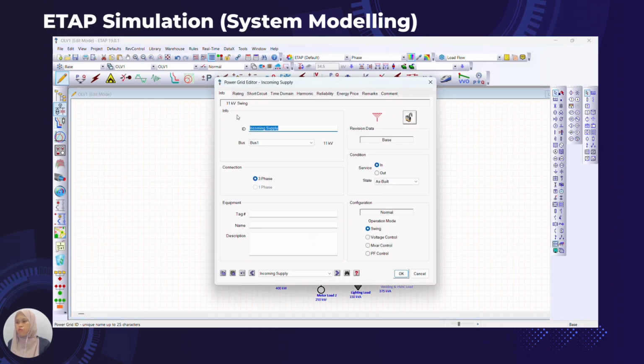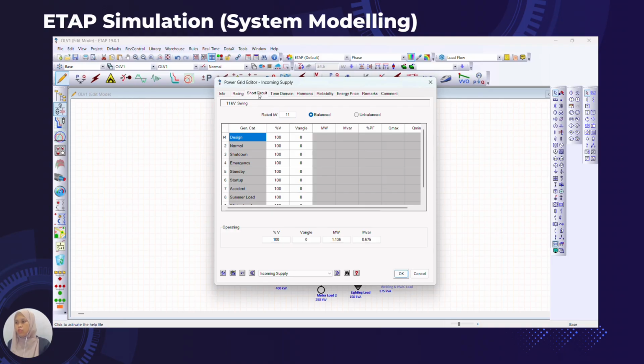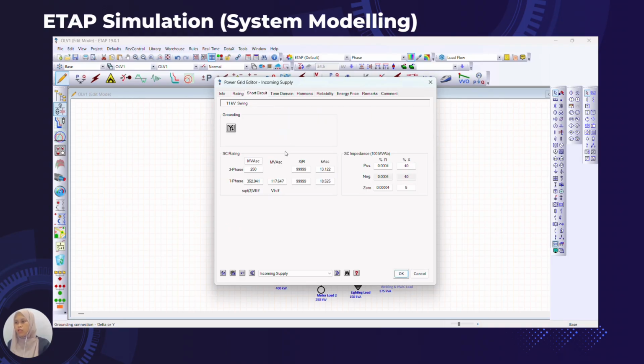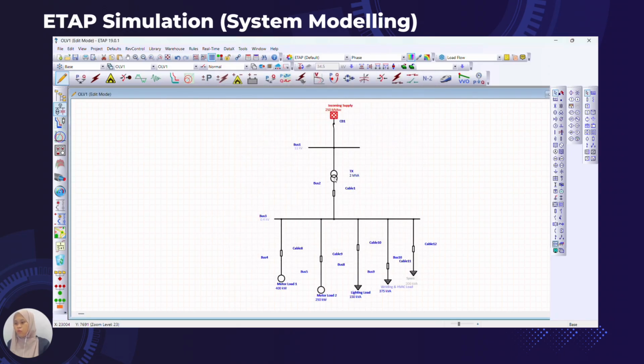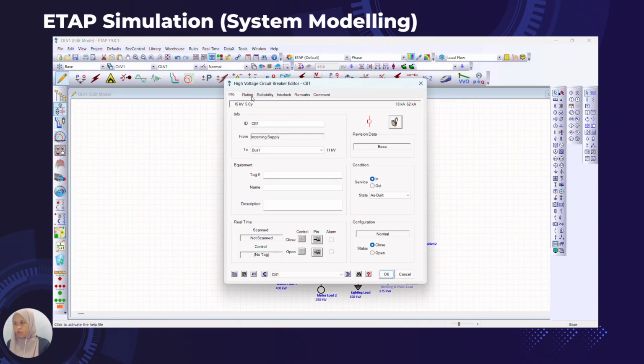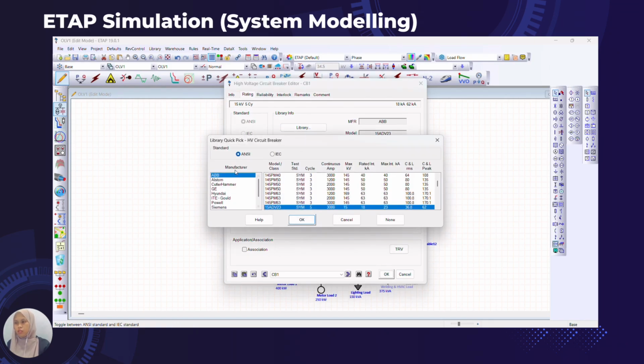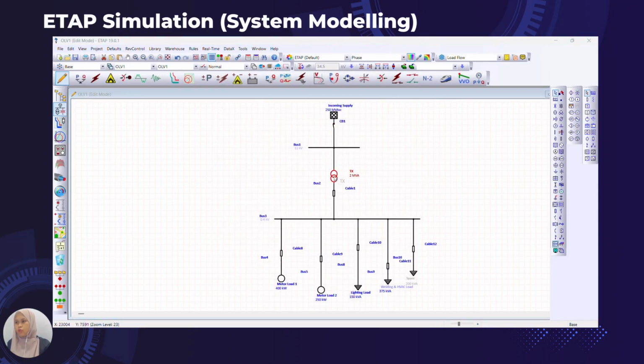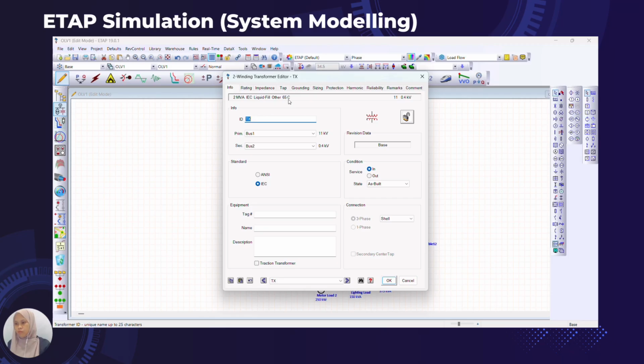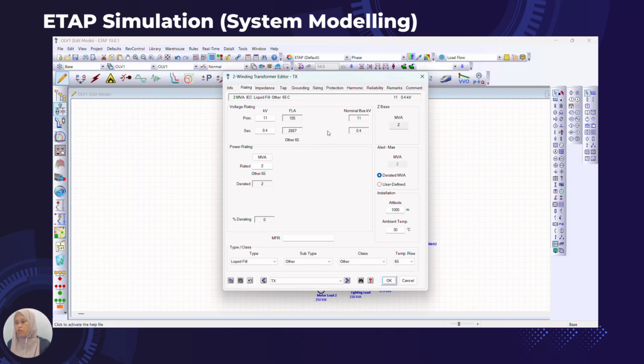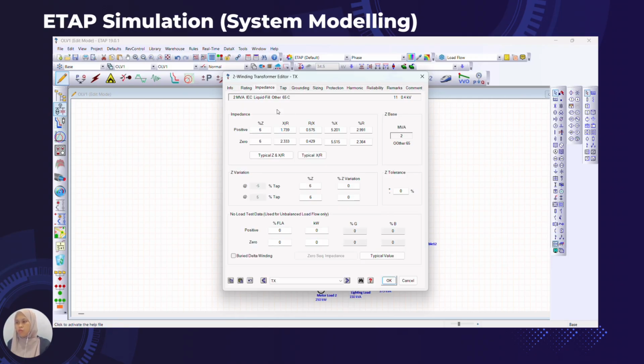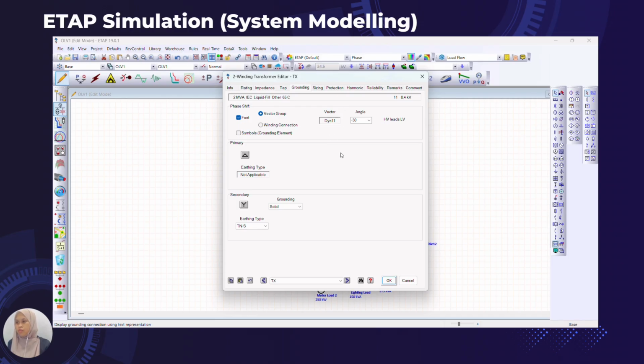So the setting for the power grid: the connection is 3-phase, the rating is 11 kV, and the short circuit rating is 250 MVA. For the high voltage circuit breaker, we use ABB manufacturer, which is standard ANSI. For the transformer, it is a step down transformer. The rating steps down the 11 kV to the 400 volt. The impedance is 6%. The vector group is Dyn11 and earthing type is TN-S system.